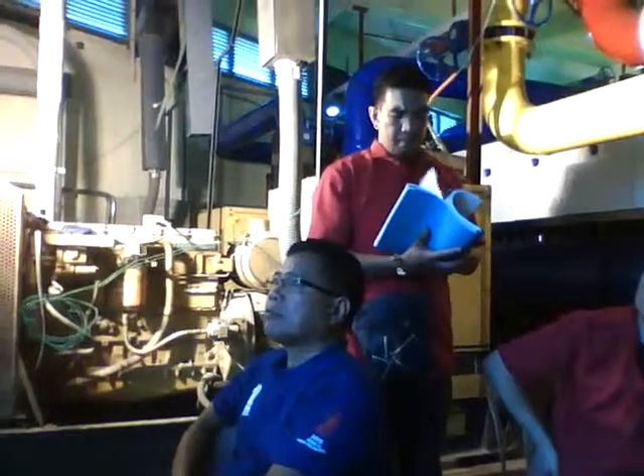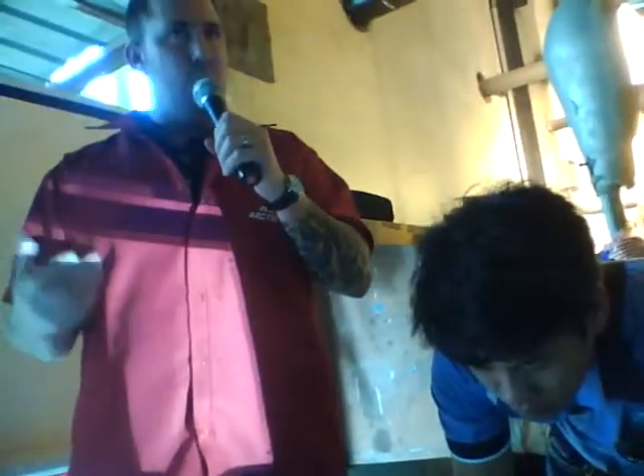You have to make sure that all your electrical connections are tight, right? Because over time, how reliable are electrical connections? There's screws, right? So you do have to make sure you go through and tighten the screws every once in a while. You also have to make sure that if you ever wanted to do a shutdown where you're going to clean your condensers, you can always run through and check the operation of the inlet guide vanes to make sure that they're all opening and closing. Perfect. So on page 89 and 90, there's all the maintenance guidelines that you can go through and check. These are all the things you should keep up with.